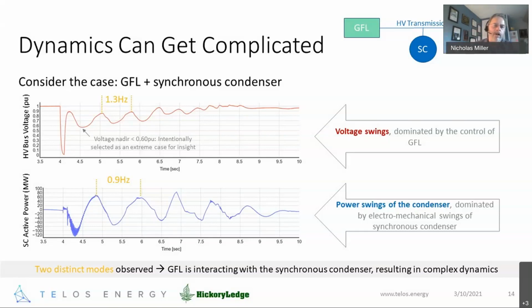And what you see here is the top is the voltage swings out at the IBR, and they're pretty ugly, and they're swinging at about 1.3 hertz. We've got that labeled in gold. The lower trace, the blue trace, is the active power swings of the synchronous condenser. And those are dominated by, as Matt keeps saying, the baggage, which we kind of like for the condenser. And they are distinctly different modes, but there is cross coupling.